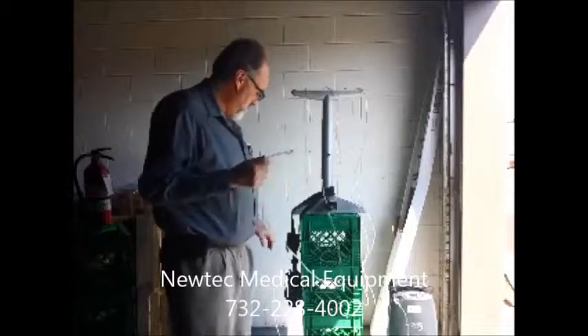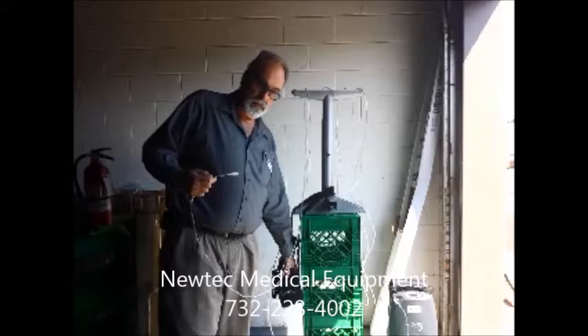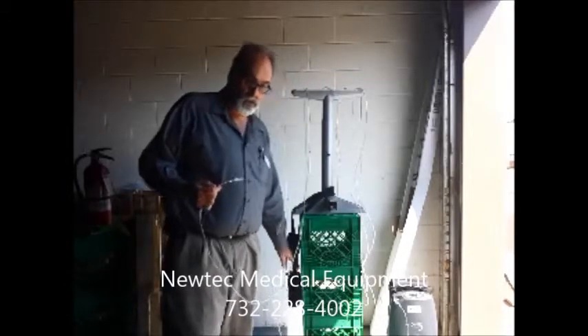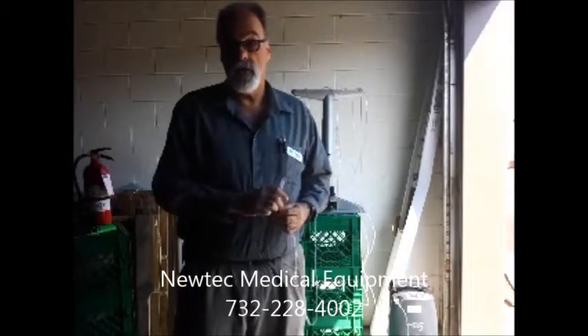Now this tube is receiving oxygen from a pulsed portable concentrator. This oxygen is only coming out in pulses. I have it set to deliver automatic pulses. Through normal operation, however, that would only provide pulses when somebody initiates a breath. So that by itself will stop the source of oxygen as soon as the tubing is removed from the patient, or if it should catch on fire — as soon as it's no longer being triggered by breaths, it will no longer be flowing oxygen.